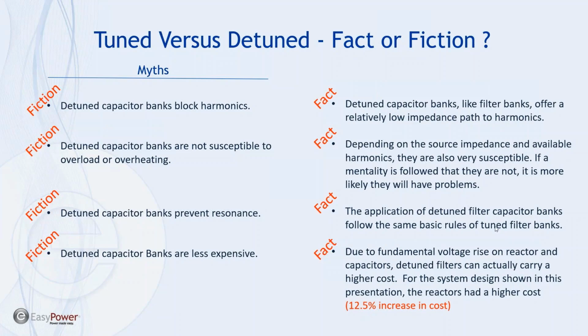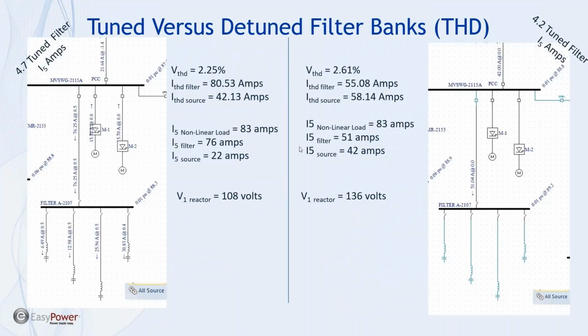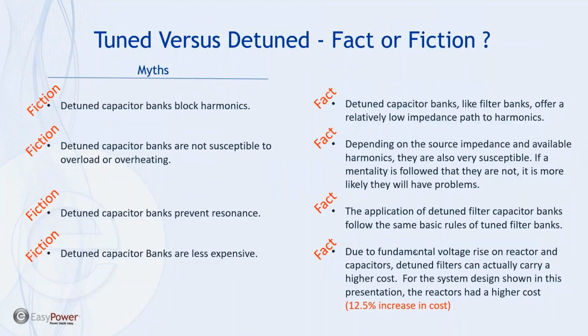And finally, detuned capacitor banks are less expensive. I think it's fair to say that the reactor in both situations needs to be designed for harmonic current. We can also say that the detuned reactor at the fundamental frequency must carry more voltage and therefore it must be made larger. So there are many cases where a detuned filter bank is more expensive. For the filter system that I provided in this presentation, we were at a value of 12.5% higher in cost for the detuned filter versus the tuned filter bank. So it's contrary to the belief of many engineers, who thought that a detuned filter system was less expensive. It simply is not.